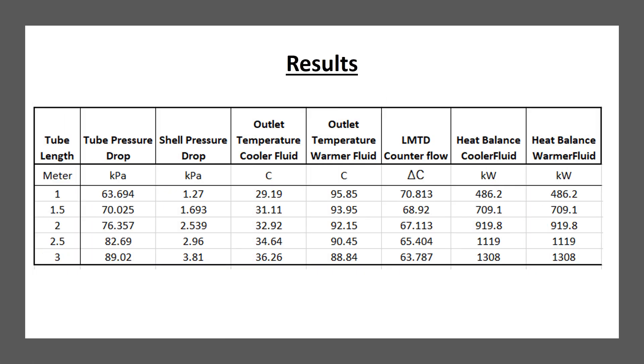Using the software MathCAD, we can find the results. As the tube length increases, the pressure drop for the tube and shell increase. The outlet temperature for the cooler fluid increases, the outlet temperature for the warmer fluid decreases. The log mean temperature difference decreases, and the heat balance for the cooler fluid and warmer fluid increase.